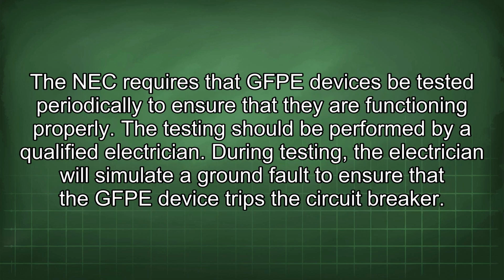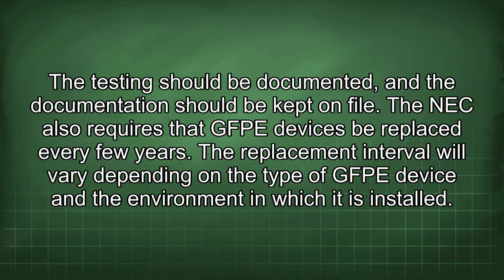The NEC requires the GFPE devices be tested periodically to ensure that they are functioning properly. The testing should be performed by a qualified electrician. During testing, the electrician will simulate a ground fault to ensure that the GFPE device trips the circuit breaker. The testing should be documented, and the documentation should be kept on file.